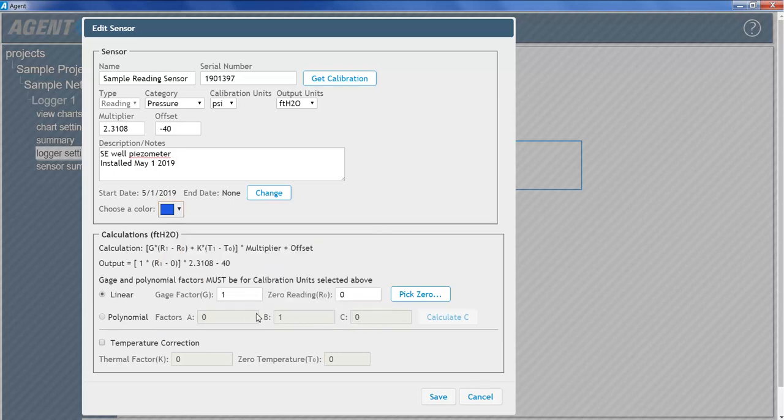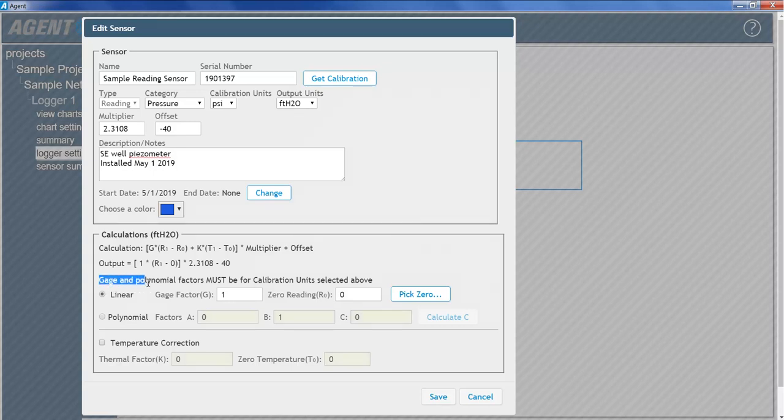The default gauge factor of 1 can be used to output the data in digits. To output the data in other engineering units, the gauge factors found on the Geokon calibration report provided with the vibrating wire sensor must be entered. Make sure that the gauge factors taken from the calibration report match the calibration units selected in Agent.